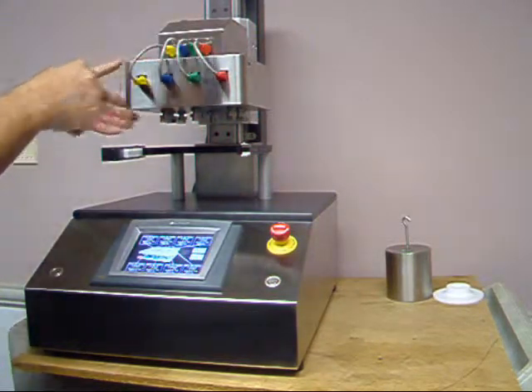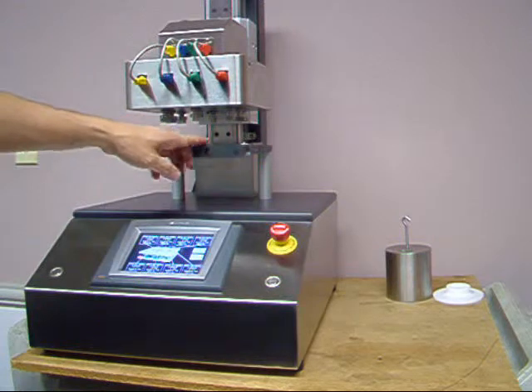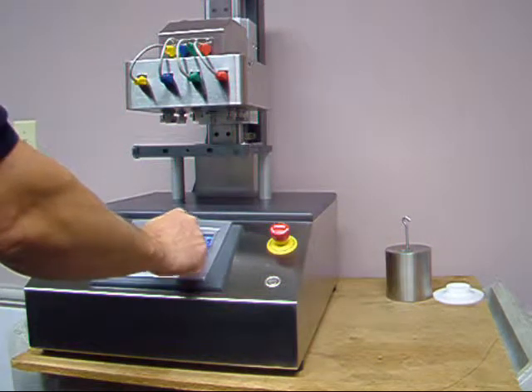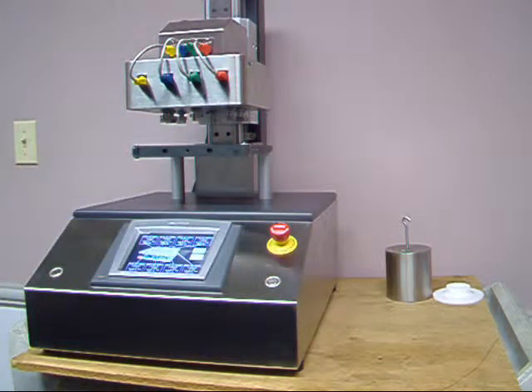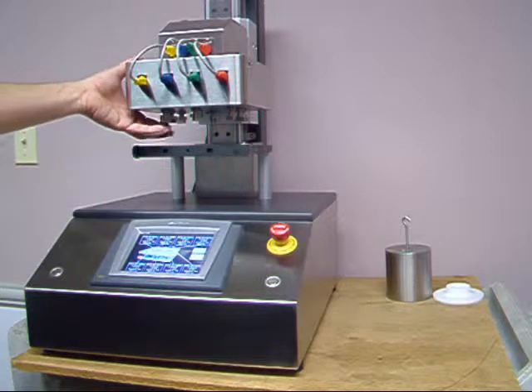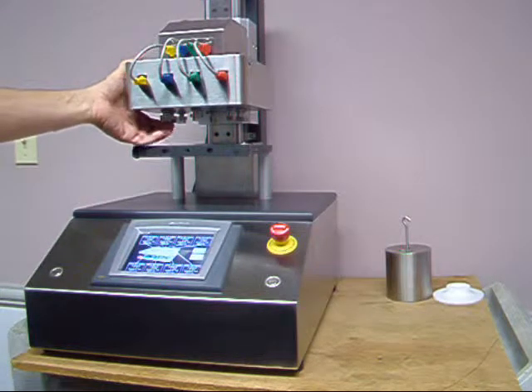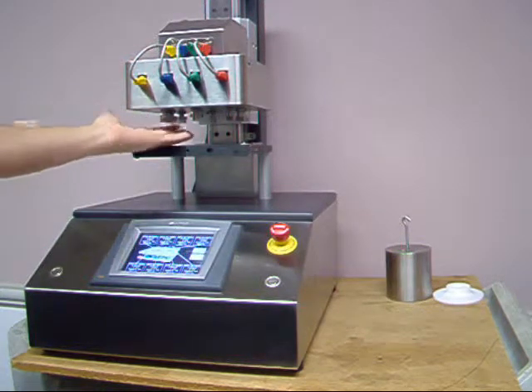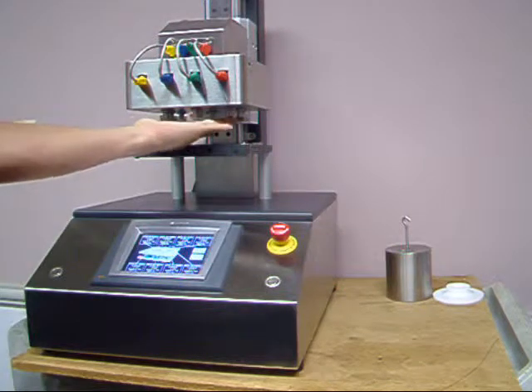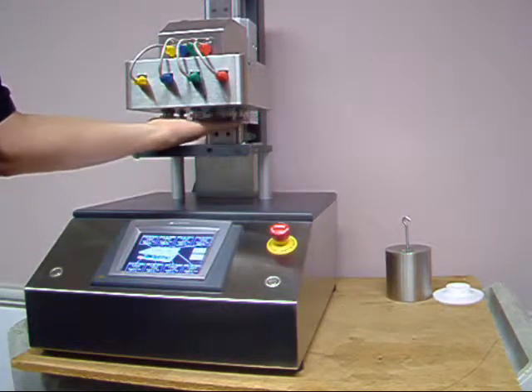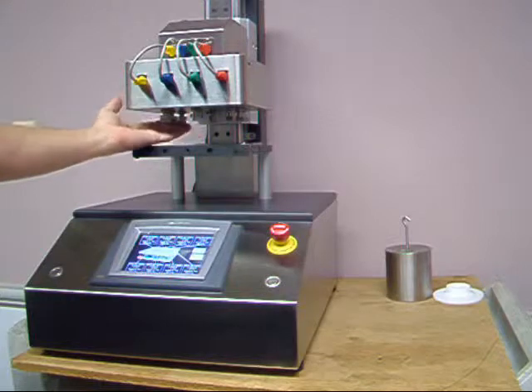Now when this is done, your offset will be off, so you have to press the 0 offset again, and that zeros the offsets, and from here on you can accurately measure the torque. And then just to make sure that all sensors are connected properly, you can start pressing on them and inspect the readout on the screen and make sure the readout is changing proportionally to the applied force.